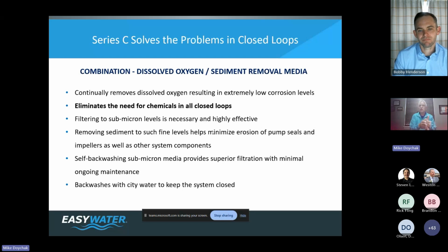Going to filter to a submicron level. That is necessary because the particles are very small, generally between about 0.5 and 5 microns. So we're going to filter to less than 1. By removing all of that stuff, not only are you going to pick up efficiency and operation, but you're going to help minimize the erosion of pump seals and impellers and all of the other system components, heat exchangers, and whatever else is in the closed loop.